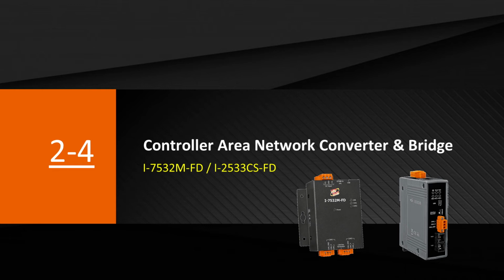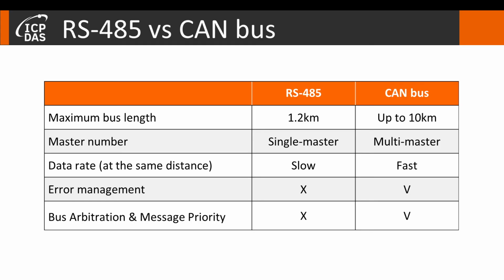Here comes the last part of the communication products, the Controller Area Network converter and bridge. Before getting to the point, let's first have a brief comparison between RS485 and CAN bus. In terms of maximum bus length, RS485 can be 1.2 kilometers, and CAN bus supports up to 10 kilometers. In terms of number of masters, RS485 only allows a single master, while CAN bus has multi-masters.